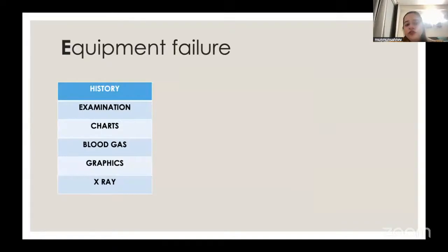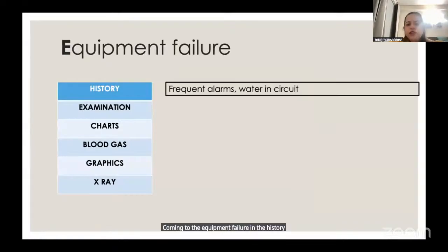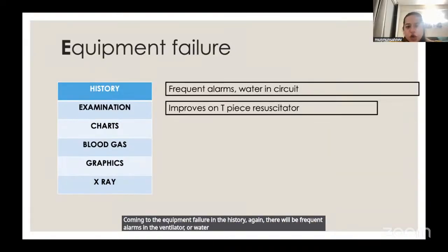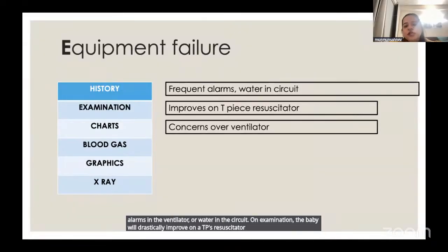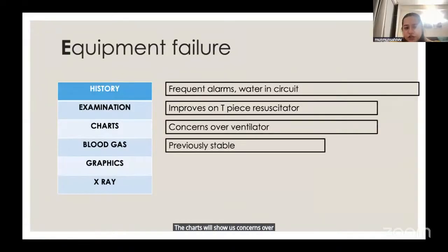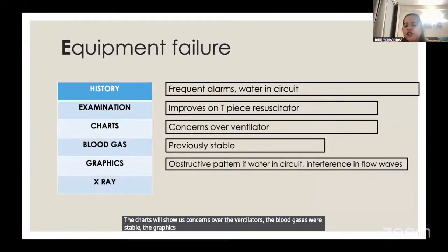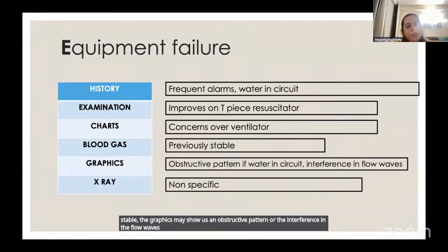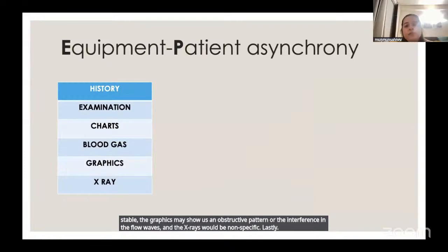Coming to the equipment failure, in the history, again, there will be frequent alarms in the ventilator or water in the circuit. On examination, the baby will drastically improve on a T-piece resuscitator. The charts will show us concerns over the ventilator. The blood gases will be stable. The graphics may show us an obstructive pattern or interference in the flow waves, and the X-rays would be non-specific. Lastly, coming to the equipment patient asynchrony.